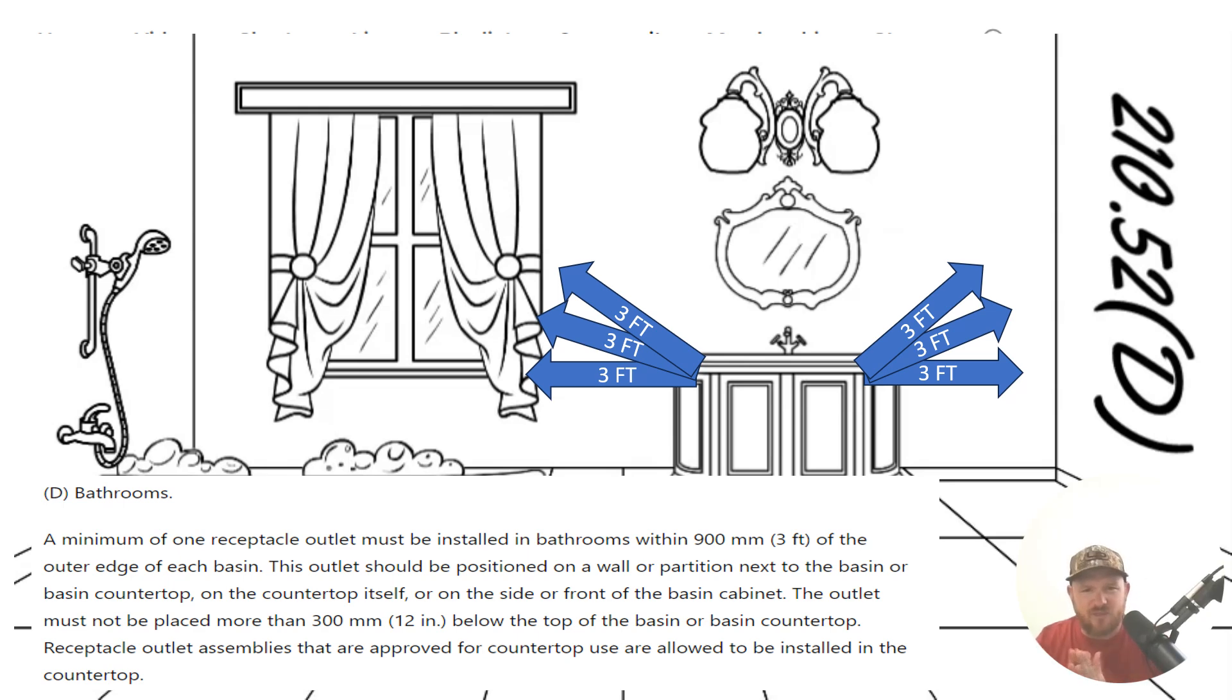We are allowed to strategically place one outlet to satisfy the three feet for both basins. That's okay, because here it says three feet of the outer edge of each basin. So it doesn't say we have to have one outlet per, but it says that we must have an outlet within three feet of each basin. And this is to keep people, like we learned yesterday, from running extension cords, especially in bathrooms.